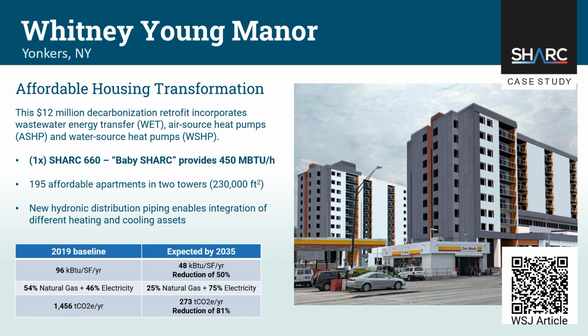Whitney Young Manor, which you mentioned earlier, is currently in construction -- I should mention Amalgamated is still in design right now, as we're trying to figure out the best way to connect those buildings. For Whitney Young Manor, as opposed to the Piranha, we use our SHARC system, which is our larger heat exchanger. Essentially, it's a very specialized wastewater heat exchanger with a specialized filter on the front end that removes enough of the large solids so we can run the wastewater through the heat exchanger for thermal transfer without it getting jammed up.